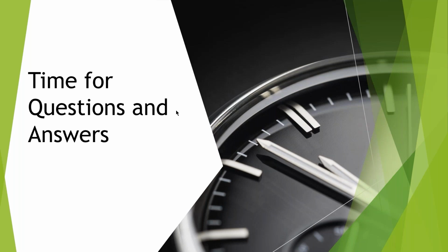You're probably gonna find all sorts of errors, and then you can start working backwards on how do I correct these errors. I have this known artifact that I can use. And then after you start correcting all the errors with that and figuring out how to make better measurements, reading the documents and doing the other stuff, now you can also use this artifact to do your statistical process controls because you bought something really, really good. This is like the gold of any lab, right? To be able to say, here is my artifact. I make a measurement once a month, whatever it may be. I'm just throwing arbitrary numbers out there. I make a measurement once a month, and all of a sudden something went bad in month 6. Well, guess what? Month 5, everything looked really, really good. So now all I have to do is look at this window: where did something bad happen between month 5 and month 6? And I'm not looking 6 months back or 7 months back.